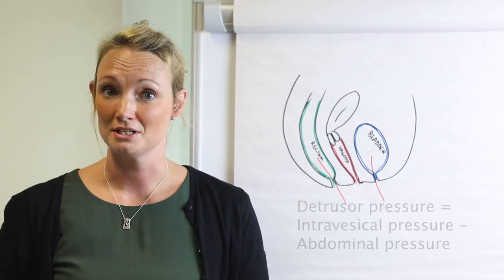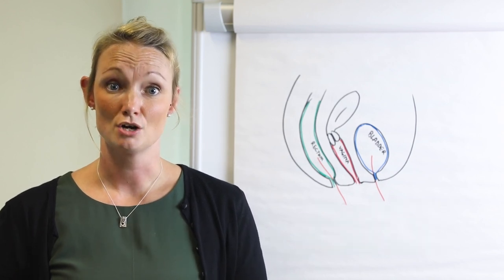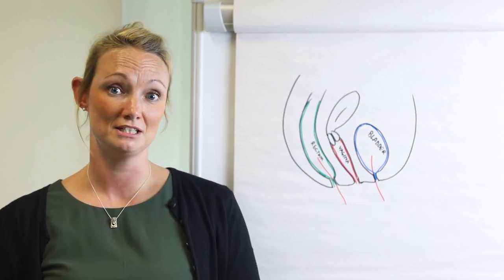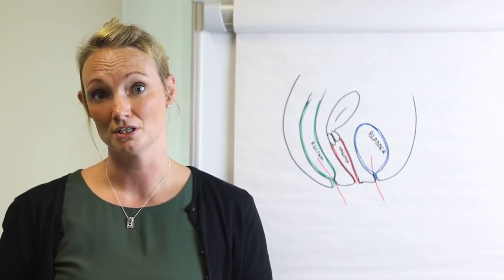The detrusor pressure is then calculated by subtracting the abdominal pressure from the intravesical pressure. A real-time graph of these pressures is generated by the software and this is viewed by the clinician to observe changes in pressure during the test.